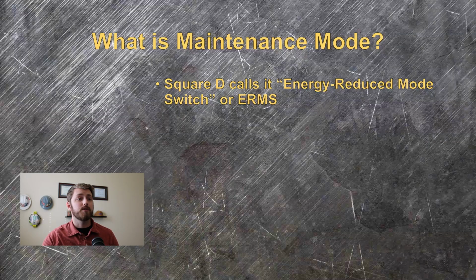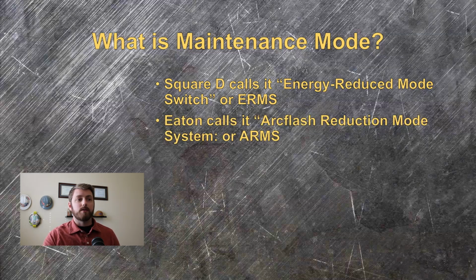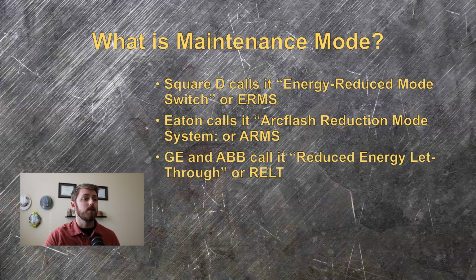Each manufacturer of switchgear and large power circuit breakers has their own name for it. So let's get that out of the way first. A generic term you might hear is energy reduction mode switch or energy reduction mode system, ERMS for short. Square D uses this nomenclature sometimes. Eaton calls it arc flash reduction mode system, or ARMS mode for short. On GE or ABB systems, it's called reduced energy let through, or RELT for short.